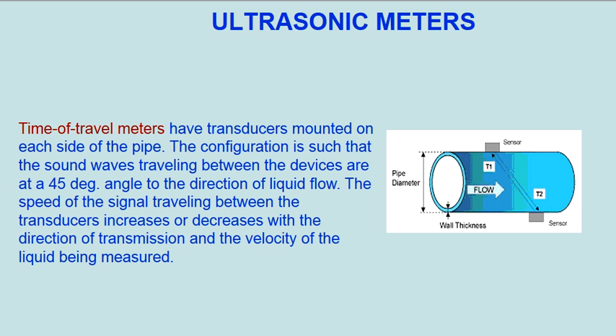Time of travel meters have transducers mounted on each side of the pipe. The configuration is such that the sound waves traveling between the devices are at a 45 degree angle to the direction of liquid flow. The speed of the signal traveling between the transducers increases or decreases with the direction of transmission and the velocity of the liquid being measured.